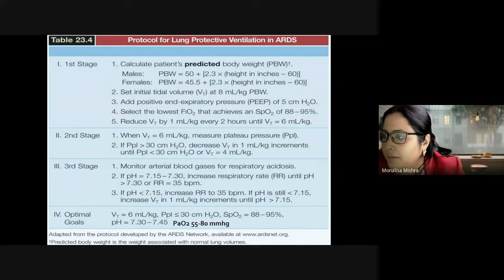And initial tidal volume, usually you set at 8 ml per kg, add a PEEP of 5, select the lowest FiO2 that is required to achieve SpO2 of 88 to 95%. Reduce the tidal volume by 1 ml per kg every 2 hours until the tidal volume is 6 ml per kg. With VT of 6 ml per kg, measure the plateau pressure. And if the plateau pressure is more than 30, decrease by 1 ml per kg until it is less than 30. And you can go as low as 4 ml per kg of tidal volume.